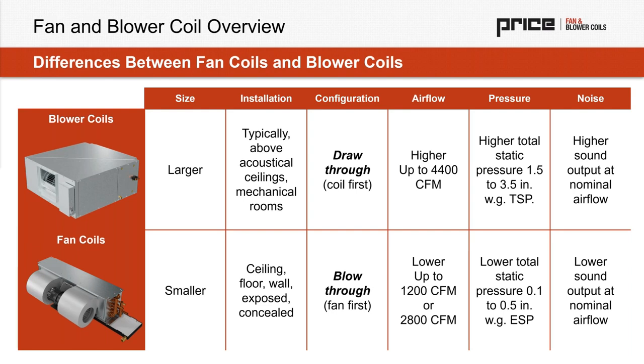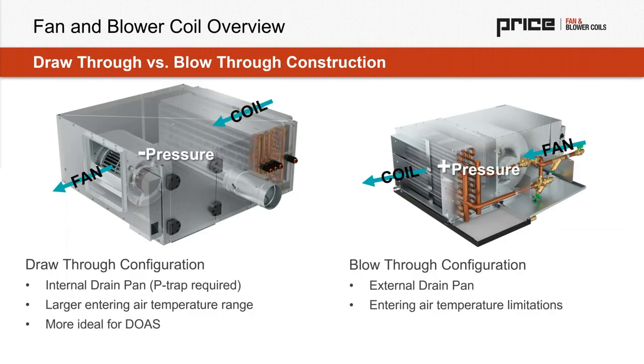However, I think one of the most impactful differences between the two is the position of the coil and the fan with respect to one another. This is confusing based off of the nomenclature, but blower coils are traditionally a draw-through product, while fan coils are traditionally a blow-through product. So to look at that in a bit more detail, we have a blower coil, the Price BCHD, on the left. We can see air enters the coil, moves through the casing, and is discharged out the supply fan. On the right, we have a blow-through product, so we have air interact with that fan first, move through the casing and discharge out the coil.